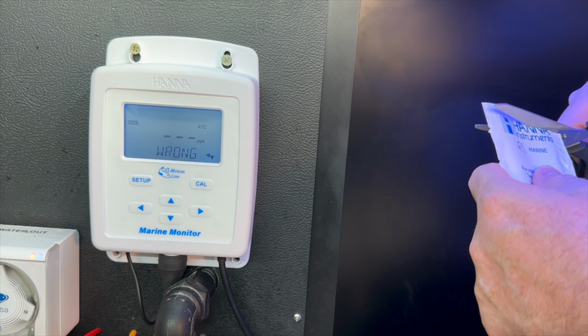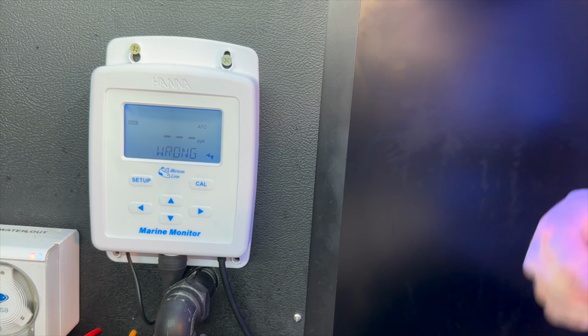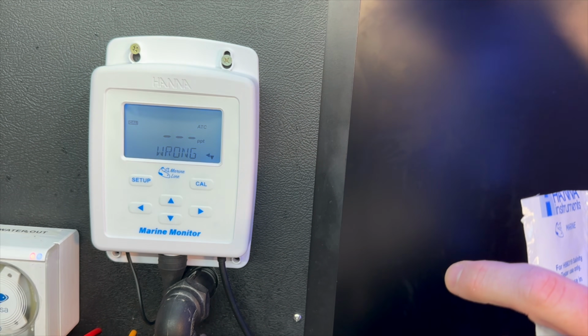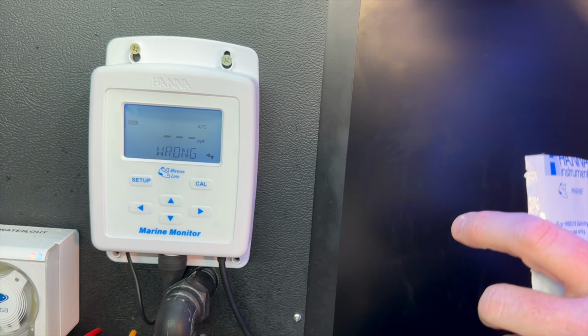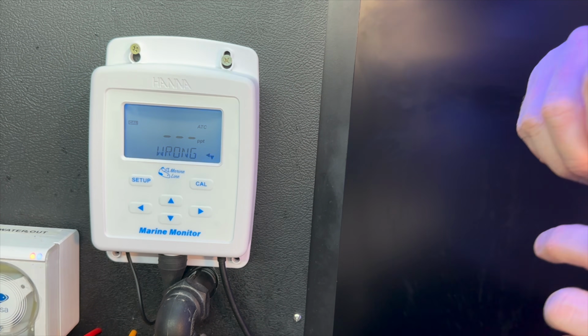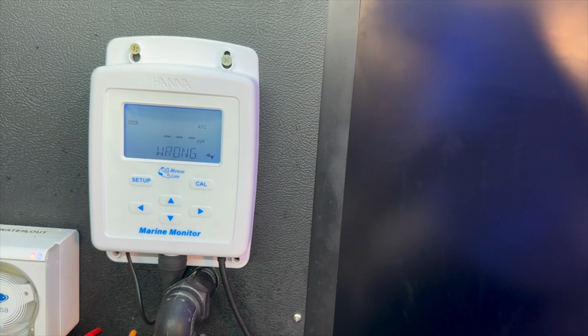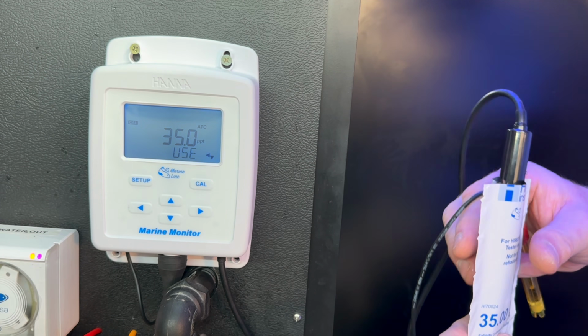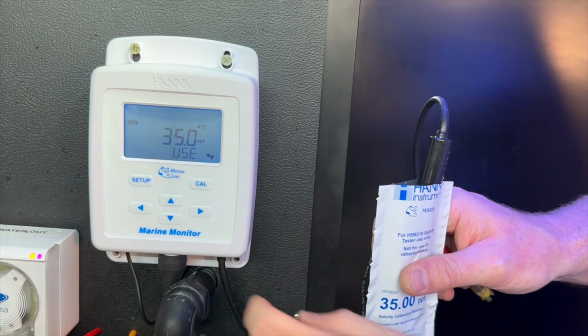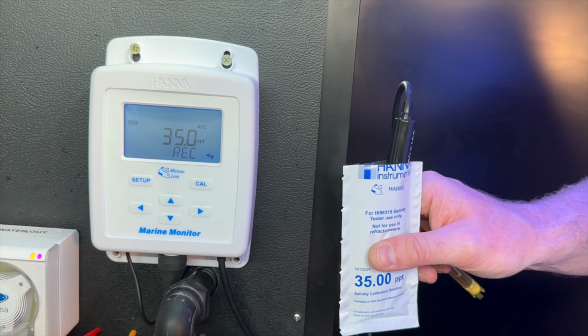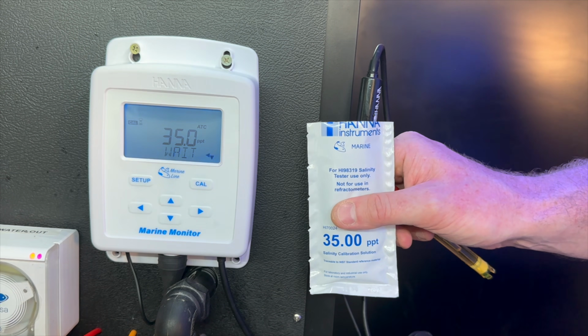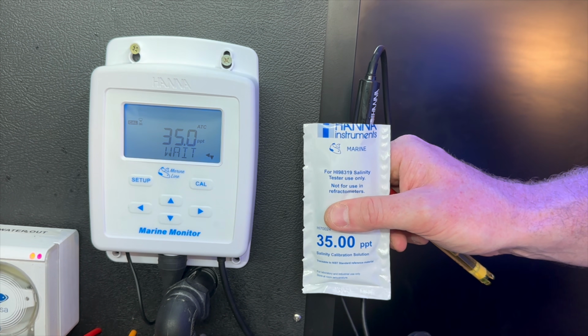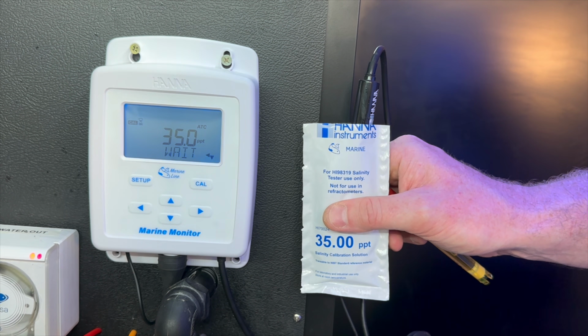And it's telling me it's currently wrong, which it is because it's not in the solution yet. Cut a little bit more off that packet. I think I haven't quite, no, I've got it open, all good. All right, let's get these probes cleaned. Okay, now there's no need to put both probes in when calibrating the conductivity fluid because the temperature compensation is on the conductivity probe. So I've got that in there. You can also put that into a plastic beaker if you don't want to get any sort of interference.